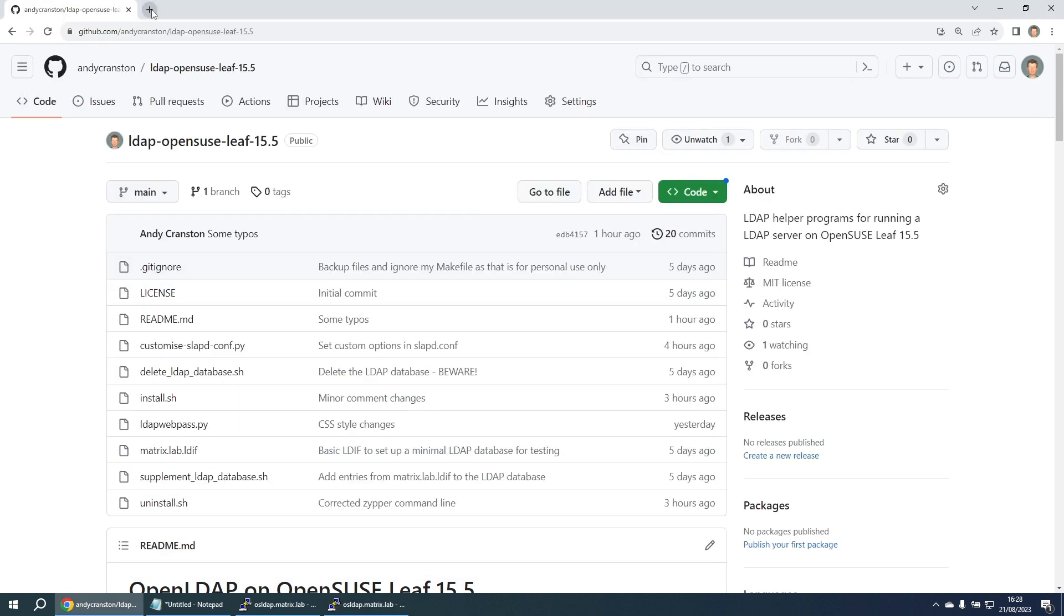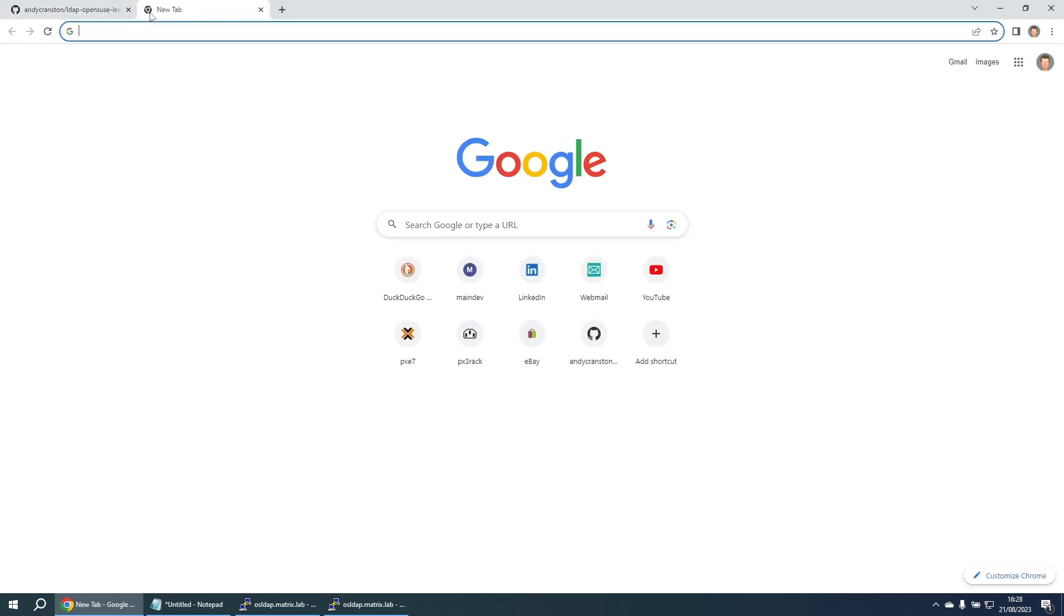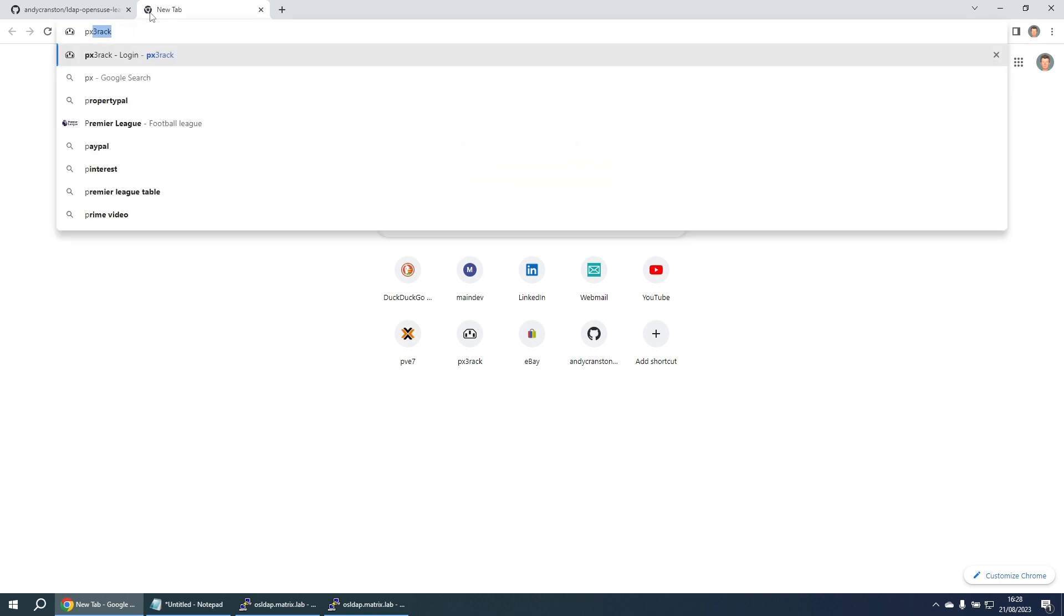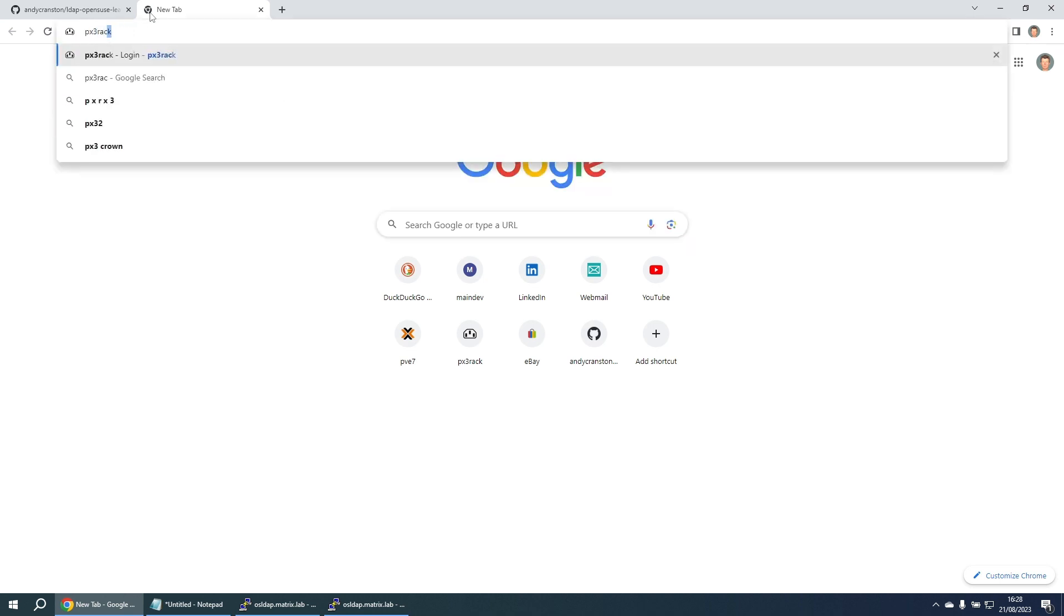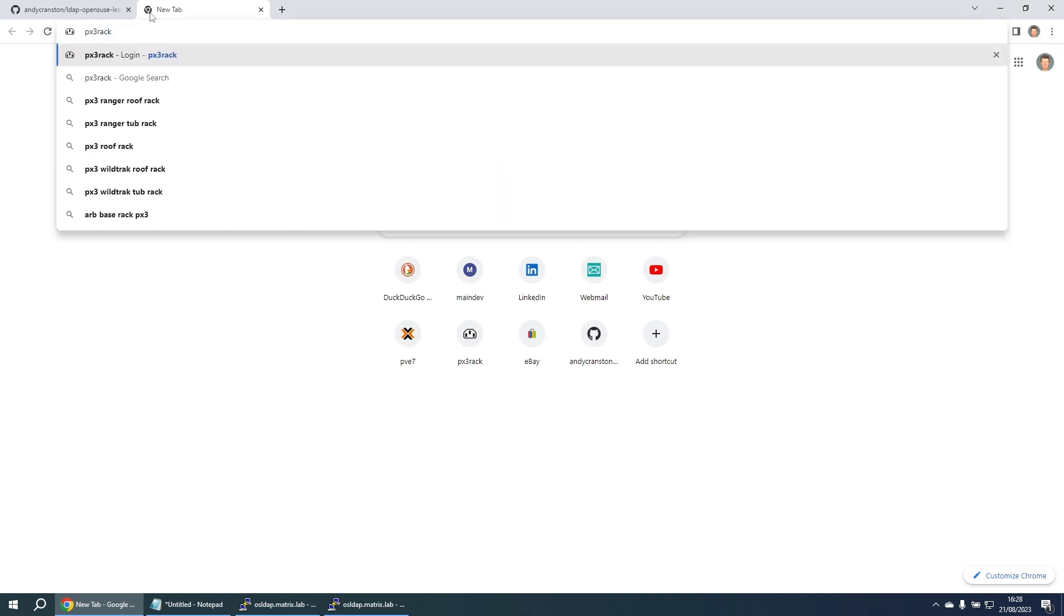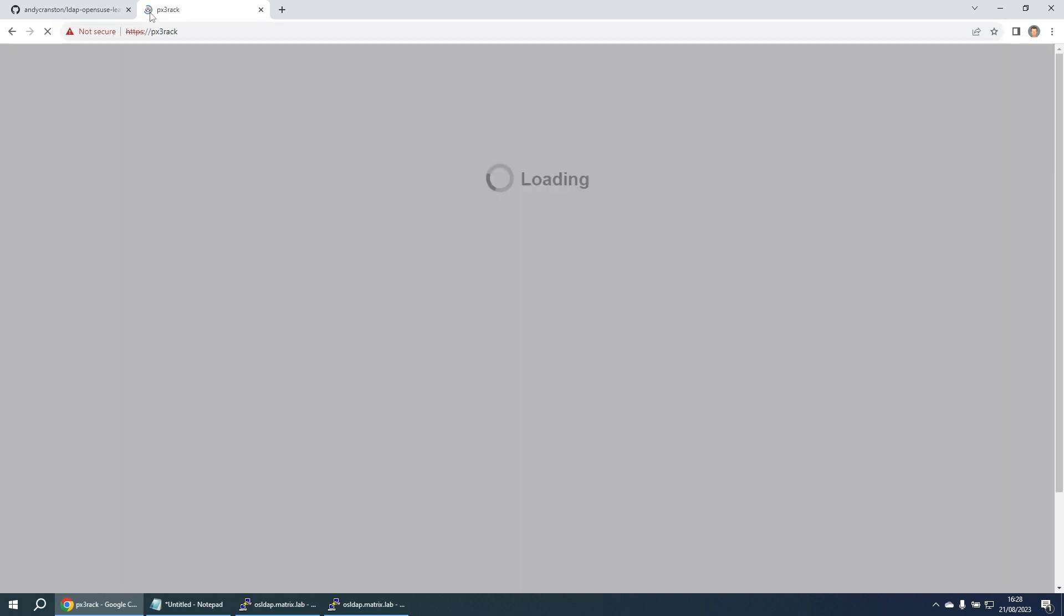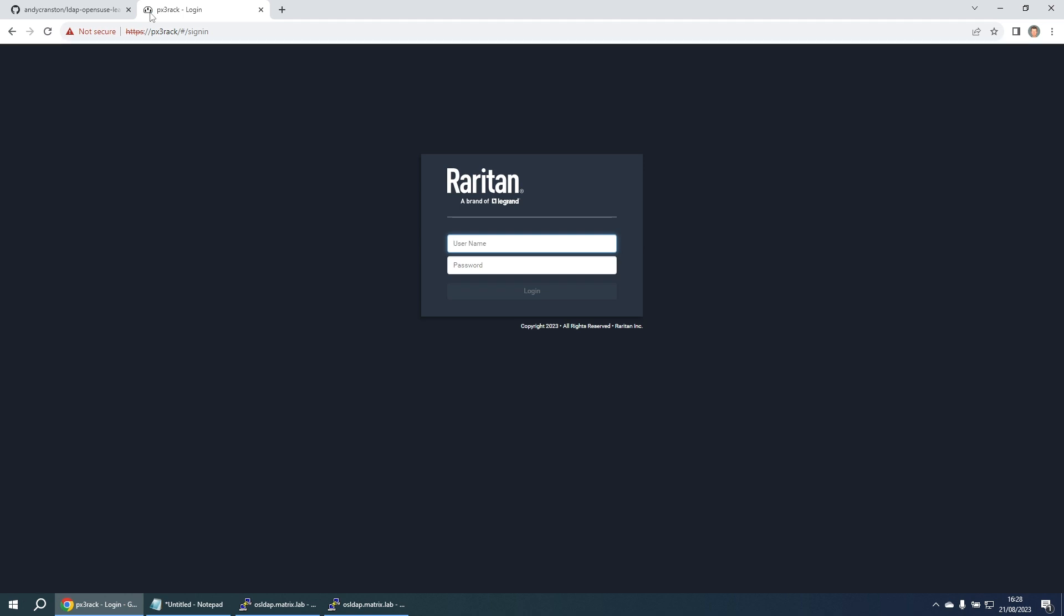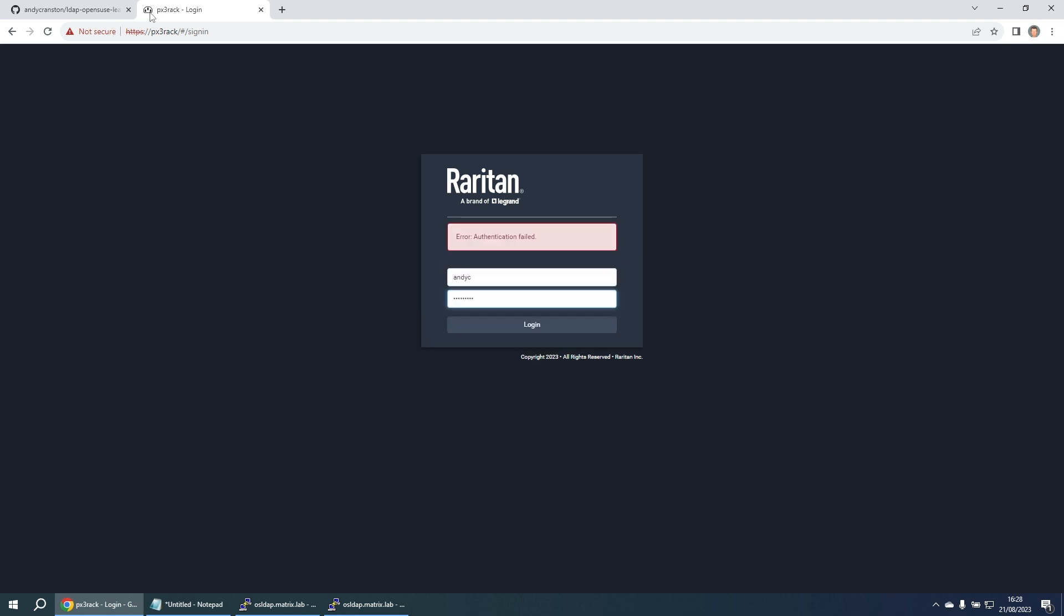Okay, so let's do a real world test of this. I'm going to log into a PX3 Raritan intelligent PDU. Now I'm going to try and log in as a user andyc with a password, and it's going to tell me that your authentication has failed. That's because this Raritan PDU isn't currently configured to use the LDAP server that holds the authentication details for that user.